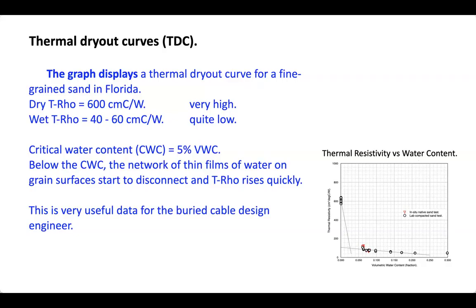Okay, well, this is a thermal dryout curve. And at 0 water content, you'll see that the dots are at a thermal resistivity value of about 600, which is quite high. But as water content increases beyond about 5 or 6%, the thermal resistivity comes down to a quite low value, and it remains low out to full saturation of the sample. And so the electrical engineers want to make sure that their soil moisture content stays in that lower range, so we don't have any very high thermal problems.